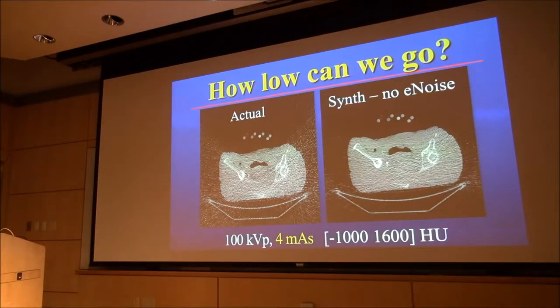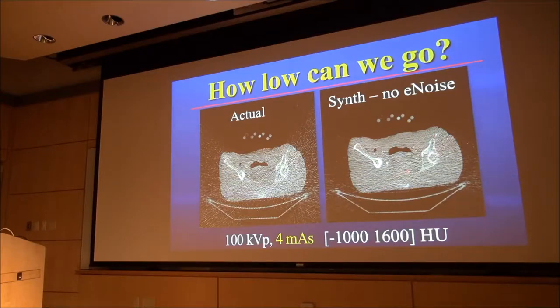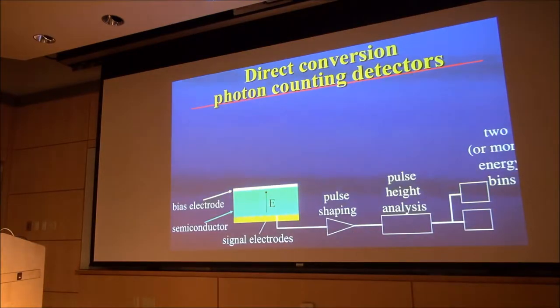Here's a demonstration. This is an actual scan of a cadaver at four MAS, very low technique, thin slice. This is what the image should have looked like if it was limited only by quantum noise. We scanned it at a high dose and predicted what the noise should look like when we reduced the dose. Big difference and all of that is coming from electronic noise.